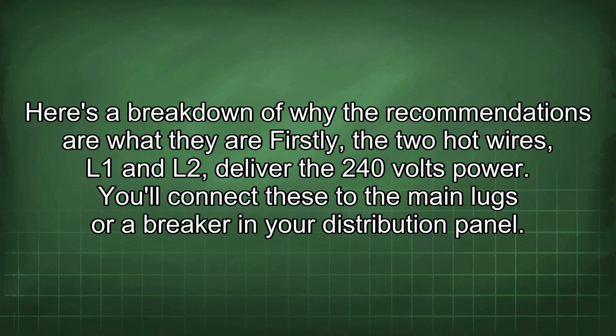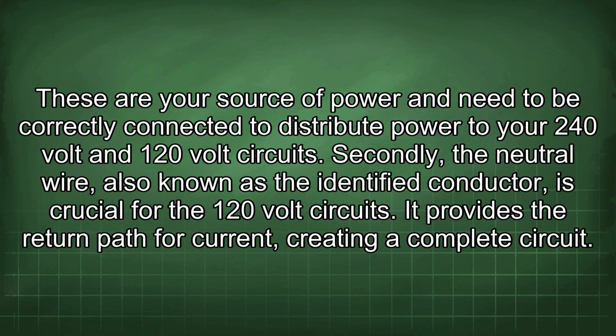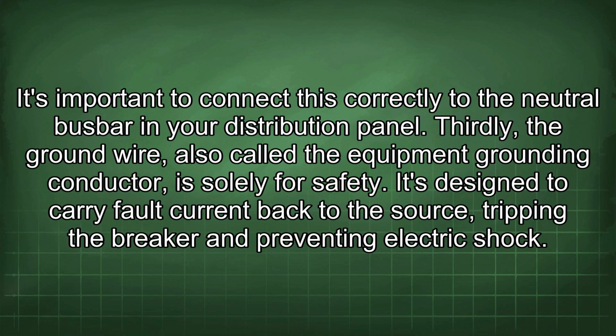Firstly, the 2 hot wires, L1 and L2, deliver the 240 volts power. You'll connect these to the main lugs or breaker in your distribution panel. These are your source of power and need to be correctly connected to distribute power to your 240 volt and 120 volt circuits. Secondly, the neutral wire, also known as the identified conductor, is crucial for the 120 volt circuits. It provides the return path for current, creating a complete circuit. It's important to connect this correctly to the neutral busbar in your distribution panel.